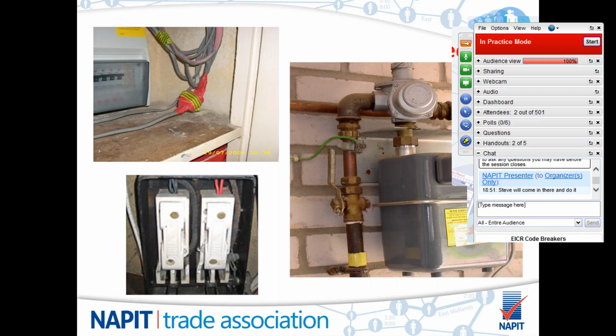Yes, first of all, there is no identification of the earthing connection. There's no BS 951 label on it. The conductor itself is obviously smaller than it should be. It's not a 10mm square cable, it's 6mm. It's green, it's not green and yellow. The biggest issue is actually the position of the clamp. It is on the incoming side of the meter. It should be on the pipe that you can see at the top, the outgoing. A continuity check between those two pipes to see if there is actually continuity throughout the meter would need to be done. If there was a continuity check, then C3, and if there wasn't a continuity check, then yes, C2. It's as if it's not bonded, yeah.